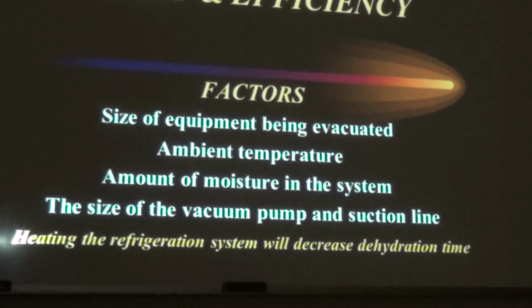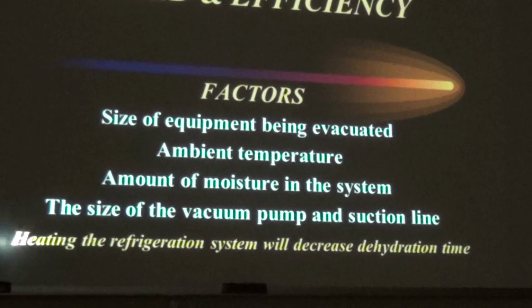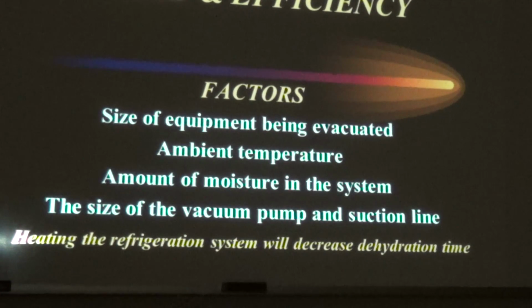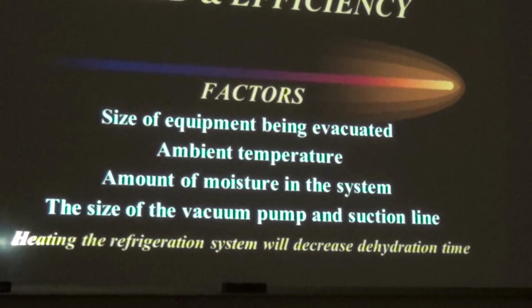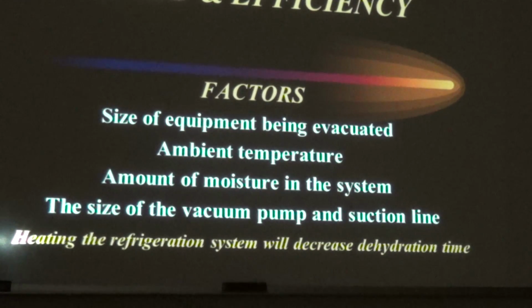What affects the speed and efficiency of doing a vacuum? Well, the first is the size of the appliance that you're working on. If it's a 50 pounds of refrigerant system, it is going to take quite a little longer than it would if it's a refrigerator. What is the outside air temperature? It's another factor that's either going to increase or decrease the speed. The other is, if it's an R22 system and it really likes water, it has a lot of moisture in the system, and you can see that the moisture indicator on the sight glass where the filter dryer is pink. Then you know, well, we've got a lot of water we've got to get rid of. And the last is the size of the vacuum pump that you're using, whether you bought it from Harbor Freight as opposed to Yellow Jacket, is going to decide how long it's going to take to get it to the proper level.